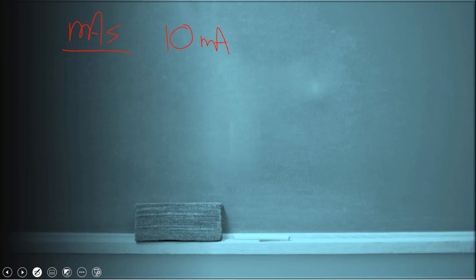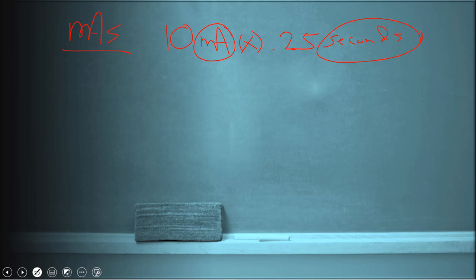Let's work through mAs on a chalkboard example. For a standard mAs unit: if you have 10 mA and multiply by 0.25 seconds, that equals 2.5 mAs. Seconds times mA equals mAs — it's that simple. Some settings use fractions for seconds, so you'd perform the same calculation. Ideally you'll have a decimal reading on your x-ray unit to calculate this easily.